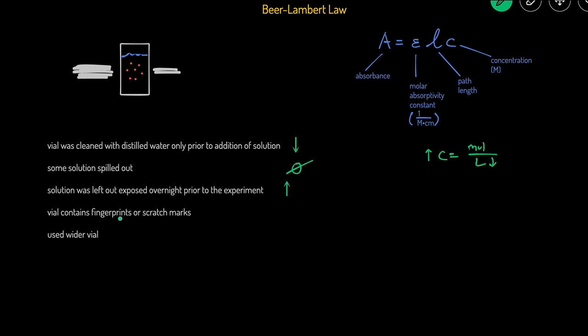Next, if the vial contains fingerprints or scratches: if the glass is not completely clean and there's some blockage, that prevents more light from passing through. The machine measures how much light gets through, so if something like a fingerprint or sticker is blocking light, less light comes through and that registers as a higher absorbance.